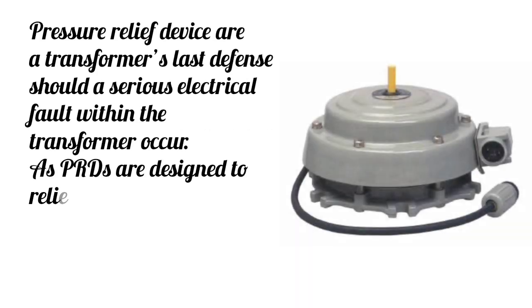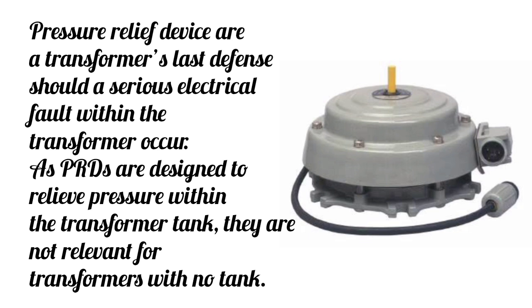PRV/PRD. Pressure relief devices are a transformer's last defense should a serious electrical fault within the transformer occur, as PRDs are designed to relieve pressure within the transformer tank. They are not relevant for transformers with no tank.